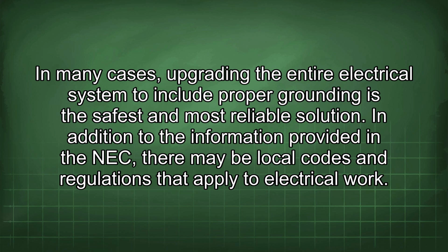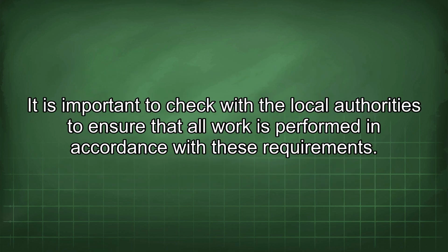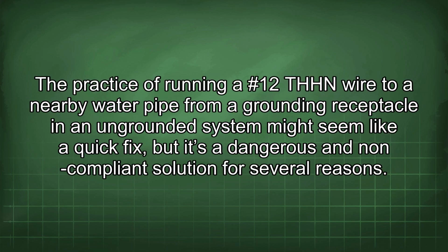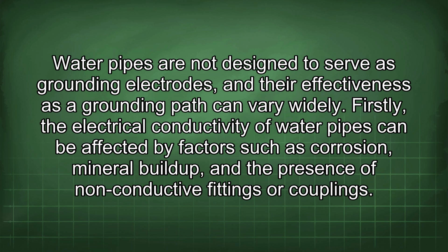In addition to the information provided in the NEC, there may be local codes and regulations that apply to electrical work. It is important to check with the local authorities to ensure that all work is performed in accordance with these requirements. The practice of running a #12 THHN wire to a nearby water pipe from a grounding receptacle in an ungrounded system might seem like a quick fix, but it's a dangerous and non-compliant solution for several reasons. Water pipes are not designed to serve as grounding electrodes, and their effectiveness as a grounding path can vary widely.